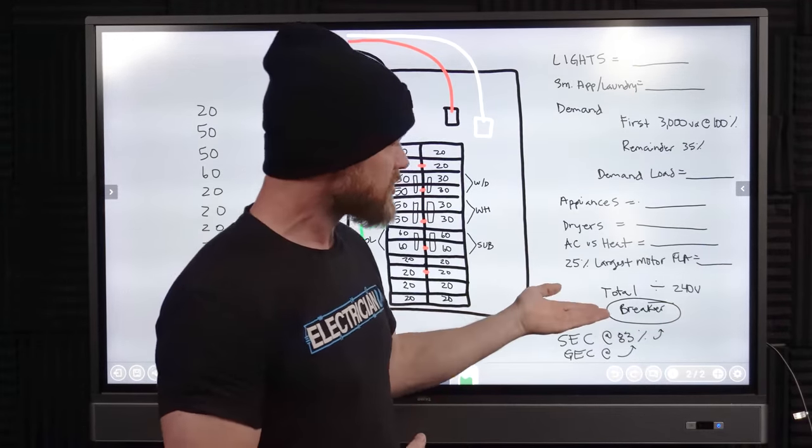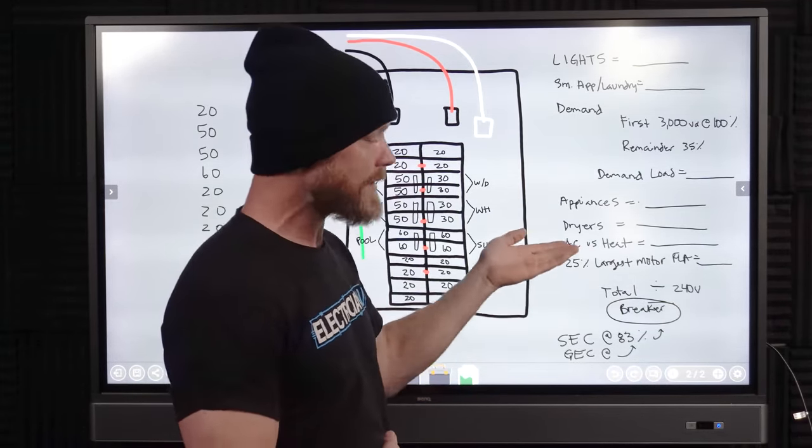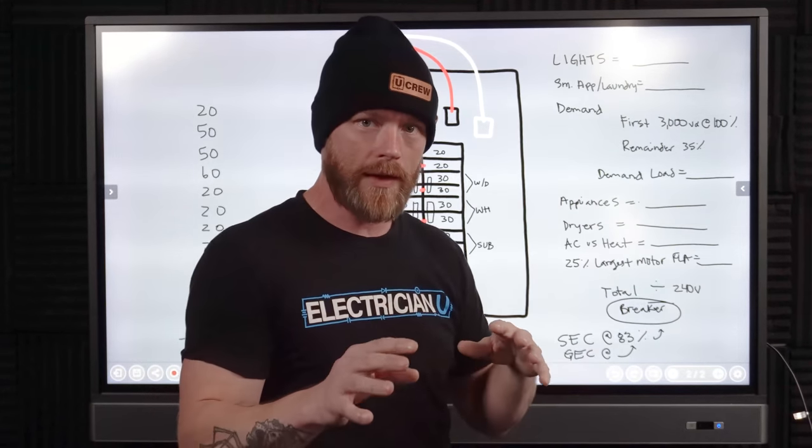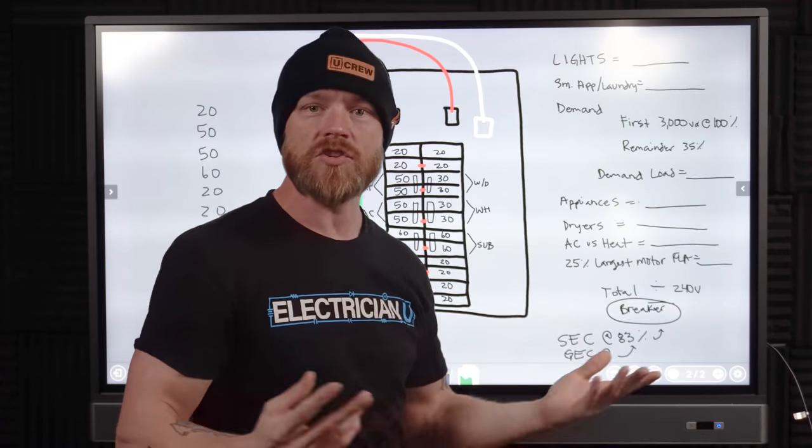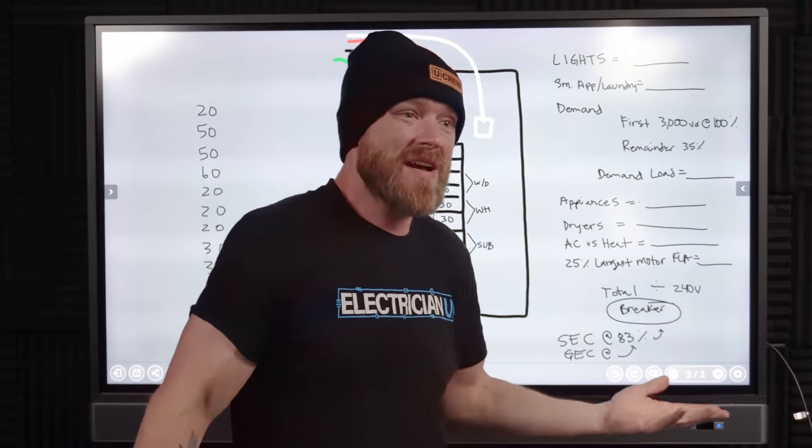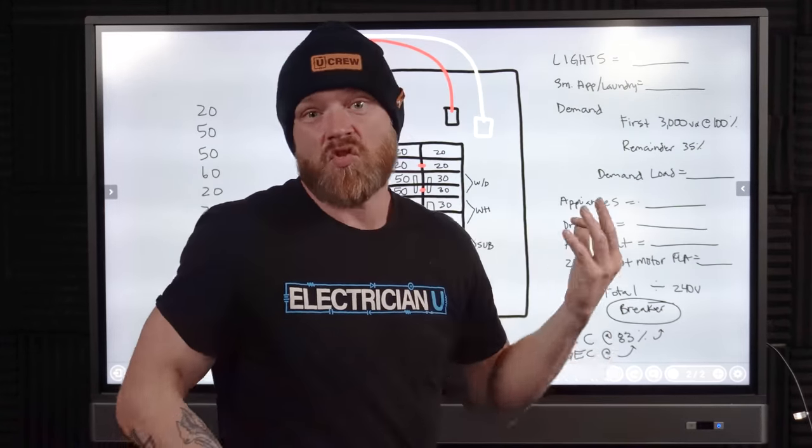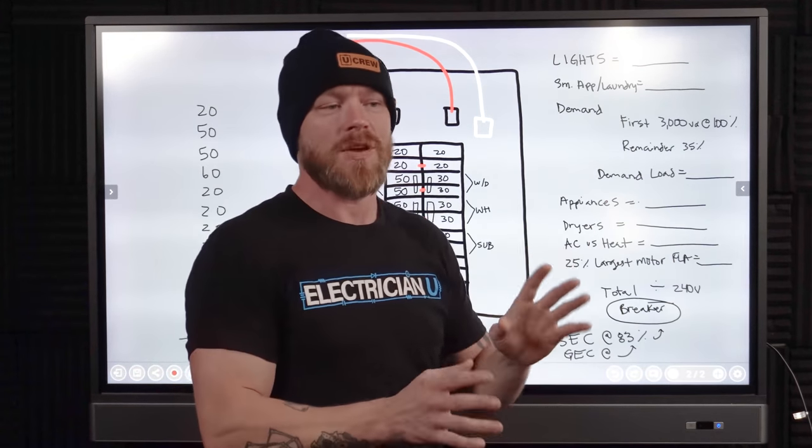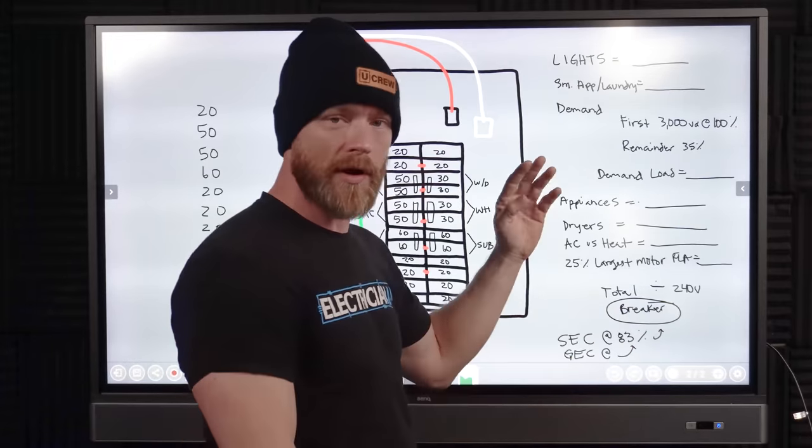So once you get all of those values and what everything are the major loads, the realistic things that are going to be running and how often they're going to be running, then we would do a total of that number and take that total number of VA or of Watts. VA and Watts aren't the same. We'll get into that in a later video, but then you would divide that by 240 volts. And that's going to come up with a breaker size. It might be like 183 or something. And so we don't make breakers that are 183. So you can round up, depending on the situation, you can round up to breakers.